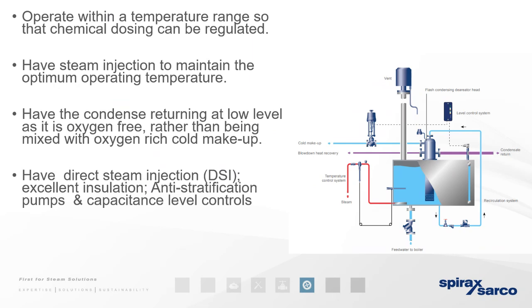As we were saying, it operates within a temperature range so that the chemical dosing can be regulated. If we know what temperature this water is because it's tightly controlled, it allows us to accurately dose the chemicals into our tank, because they will be rated to a certain gradient of temperatures. Steam injection maintains the operating temperature, so you can see it there in red. And condensate returns at low level as it's oxygen free, so we're bringing the condensate in lower so that we're not exposing it to air. And direct steam injection, for insulation, anti-stratification pumps, and so on. I'll breeze through that, but if you have any questions, please add them, and I will go back.